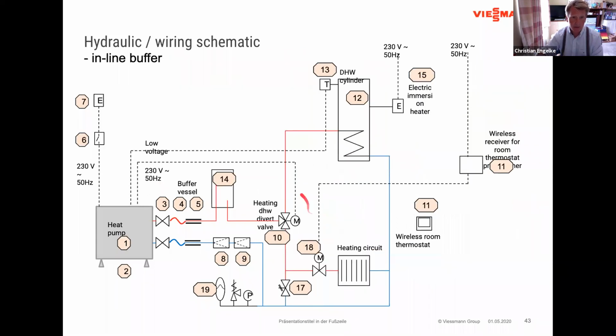And then this one here, that schematic is probably currently the most commonly used in the UK. Again, outside unit here with pipes going directly into the property, 3-port valve switching between a separate hot water cylinder and then directly into the heating circuit. Last time I discussed the need for a minimum water volume because of the defrost cycle the air source heat pump will naturally go through. So if the minimum water content is not achieved, you have to put some provisions in there to increase the minimum water volume with a wall-mounted buffer store.